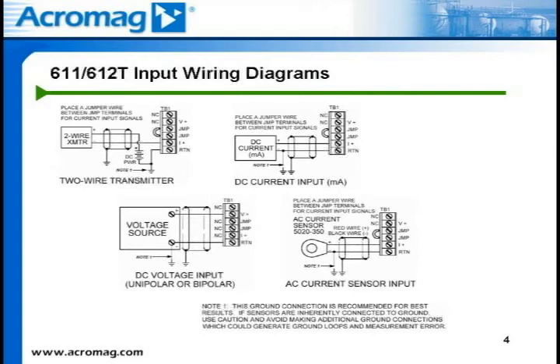The next application involves the monitoring of a DC voltage source. This can be either a unipolar or bipolar input voltage signal. As you can see, it's as simple as connecting field device positive with the V+ terminal of the 611 or 612T and the field device negative with the RTN terminal of the 611 or 612T module. No jumpers are required for this application.